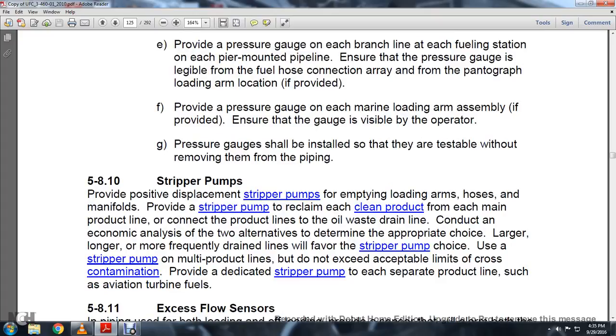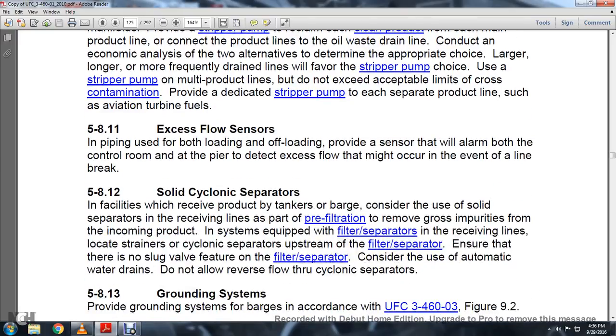5810 stripper pumps. Provide positive displacement stripper pumps to empty loading arms, hoses, and the manifold. Provide a stripper pump to reclaim clean product from each main product line. Connect the product lines to the oily waste drain line, conducting an economic analysis of the alternative approach of choice. Larger, longer, or more frequently drained lines will favor the stripper pump choice. Use a stripper pump with multiple products only if it does not exceed acceptable limits of cross-contamination. Provide a dedicated stripper pump to each separate product line, such as aviation turbine fuels.